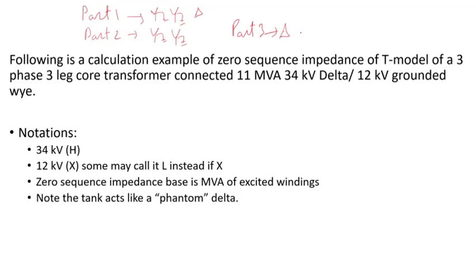Following is a calculation example for the zero sequence impedance T-model of a three-phase, three-leg core transformer connected 11 MVA, 34 kV delta, 12 kV grounded Y. The high side of 34 kV is called H, and 12 kV is called X — some may call it L instead of X; they mean the same thing. The zero sequence impedance base is the MVA of the excited winding, so in this case both high and low side are 11 MVA, which will be the base MVA.